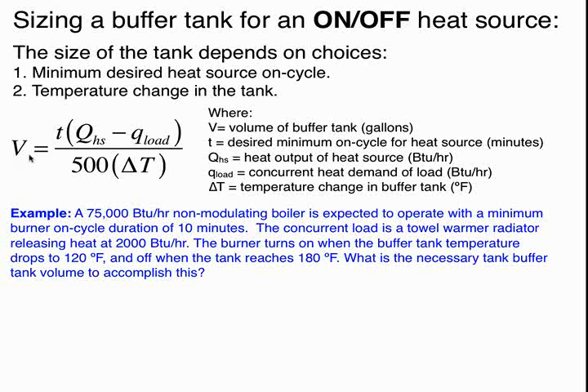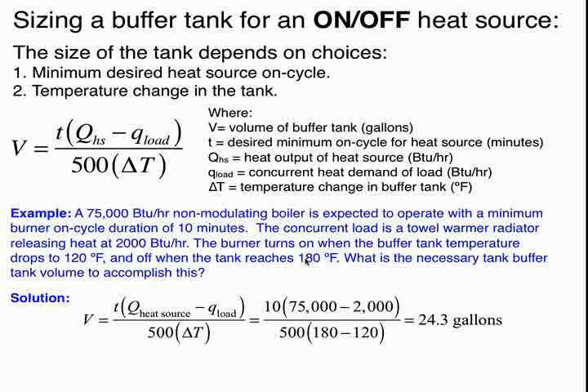Let's say we have a 75,000 non-modulating boiler, and we want to set it up for a minimum on cycle of 10 minutes. Oh, I'm sorry, I skipped T. Small t over here is the minimum on time that we want that heat source to operate at. Let's assume we have a concurrent heating load, a small towel warming radiator at 2,000 BTUs per hour, and our controls on the buffer tank are going to turn on the heat source when it drops down to 120 degrees Fahrenheit, turn it off when it goes up to 180. So we have a delta T of 60.